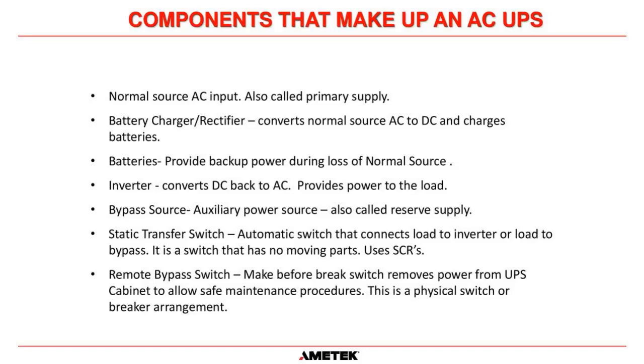Here are the main things about a UPS that you need to know. First, you have a normal source AC input — also called the primary supply — which is the three-phase AC that goes into the rectifier charger system. Then we have a battery charger or rectifier, which converts the normal source AC into DC, feeds the inverter bus, and also charges the batteries. The batteries are there only to provide backup during a loss of the normal AC source.